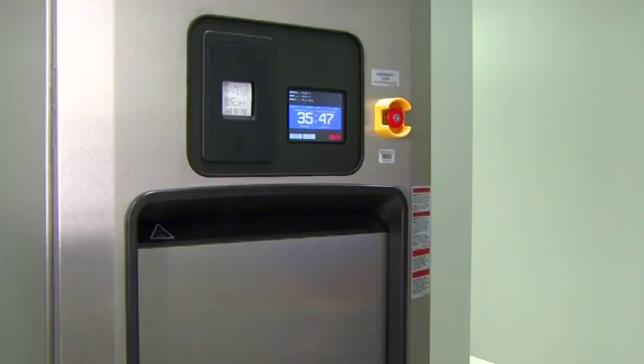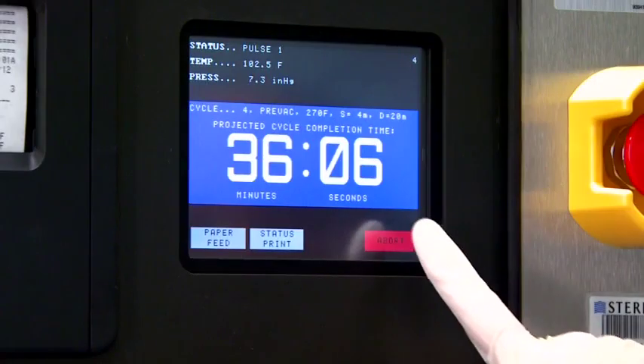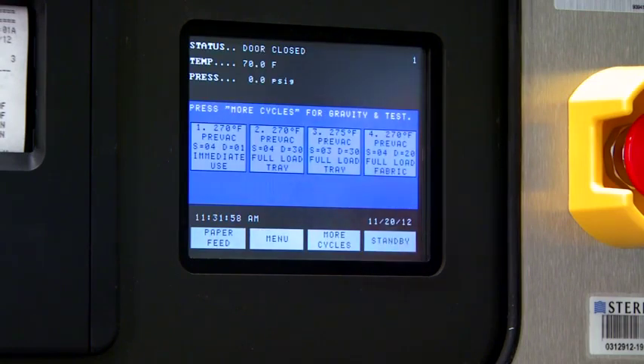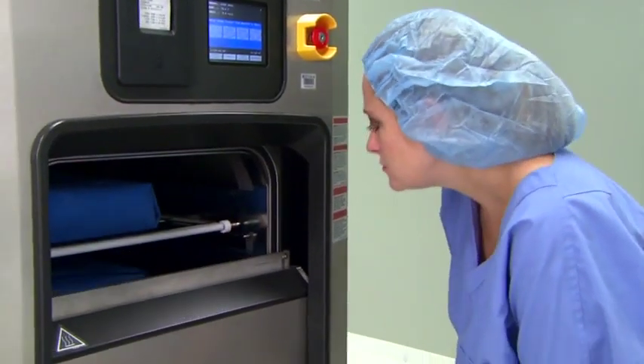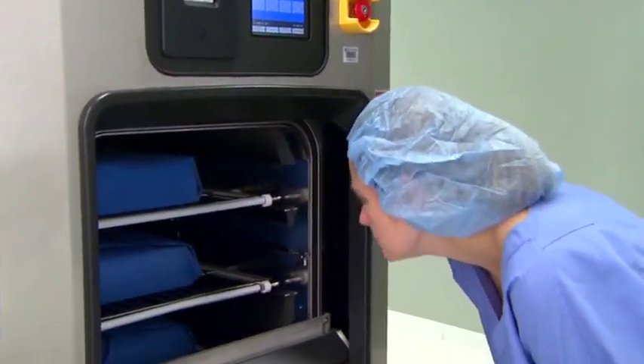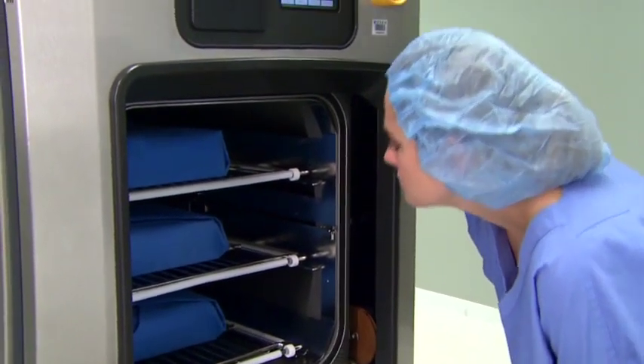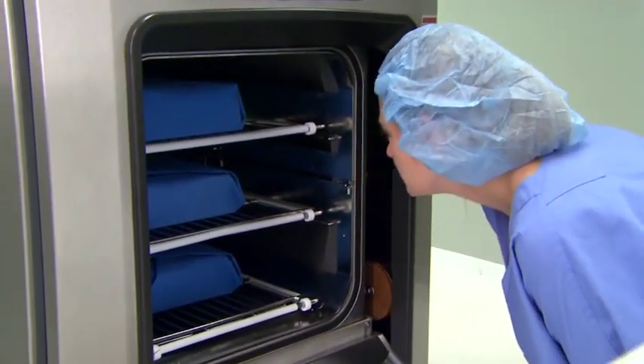At times, there may be an occasion to end a cycle before it finishes normally. For this, use the Abort touchscreen pad. A cycle only needs to be aborted if an abnormal condition or a control problem develops during the cycle. Pressing abort causes the sterilizer chamber to depressurize if pressurized, or air break if in vacuum. The door seal deactivates, the control prompts the operator to open the door, and the sterilizer returns to its normal out-of-cycle state. If an abnormal condition persists after fully aborting the cycle, contact your supervisor or a qualified service technician before trying to operate the sterilizer further.